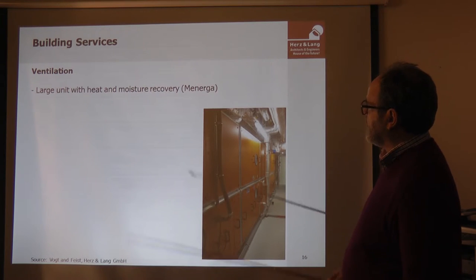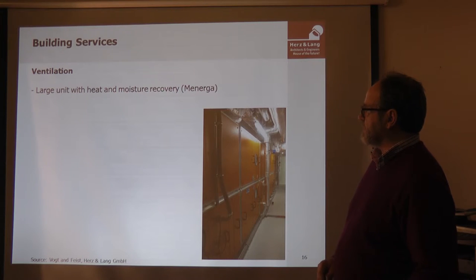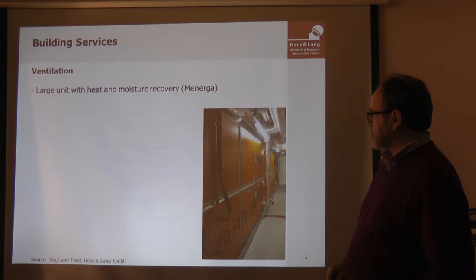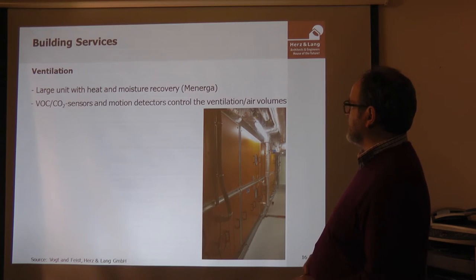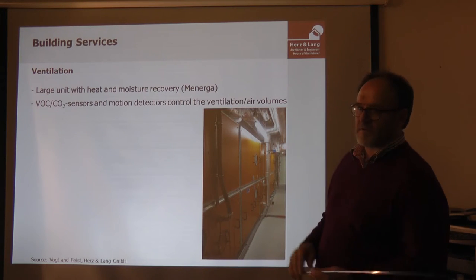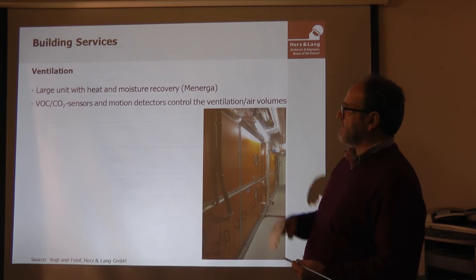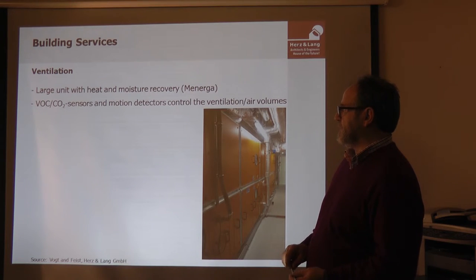This is a large Menerga unit, normally used for buildings with these high climate requirements. It is a heat and moisture recovery system with 90% heat recovery in practice. In addition, VOC and CO2 sensors control the air quality, allowing energy demand to be kept very low depending on how densely the building is occupied by visitors.